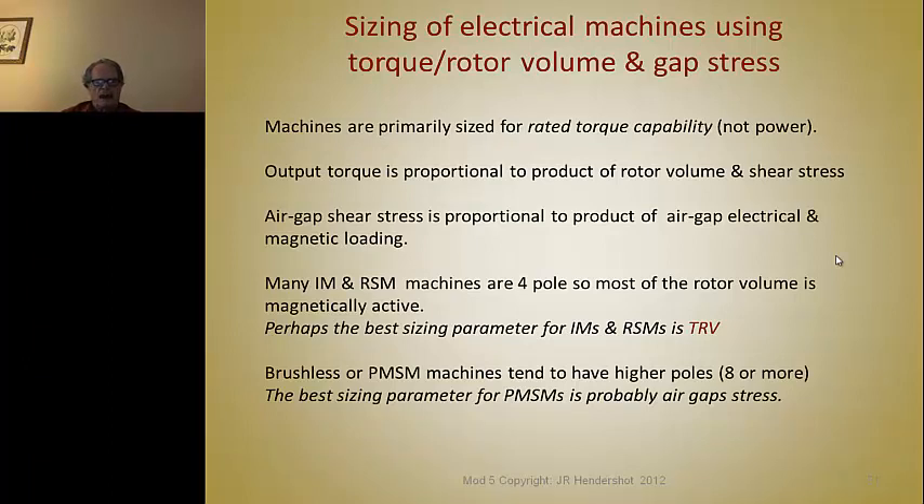The torque versus rotor volume, or TRV, is probably a very convenient way to size induction motors and reluctance synchronous motors. However, for brushless motors or PM synchronous machines, they tend to have a higher number of poles — eight poles or more. Some torquers and direct-drive wind turbine permanent magnet generators can have as many as 100 poles or more, depending on how large they are, because they operate at very low speed.